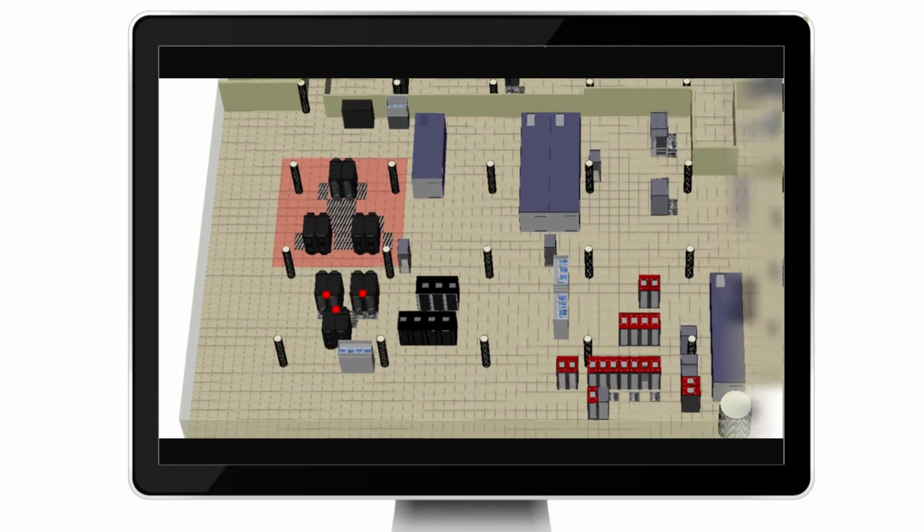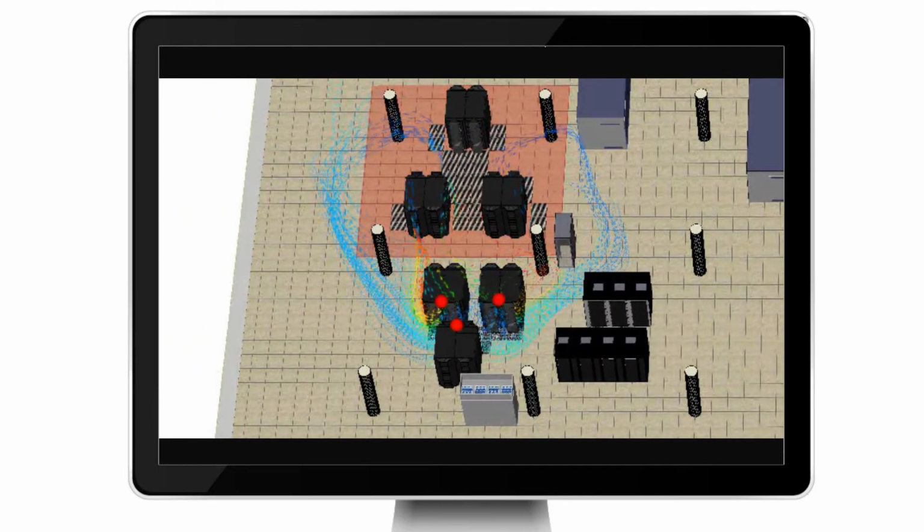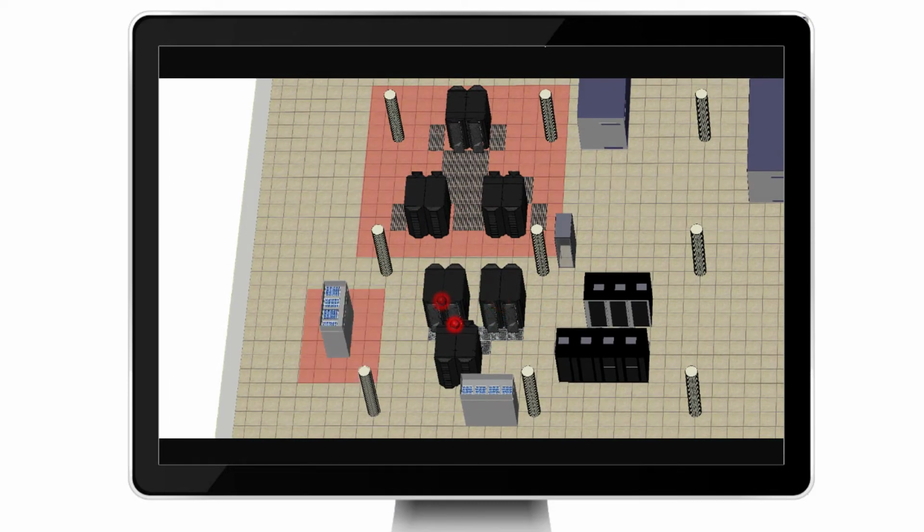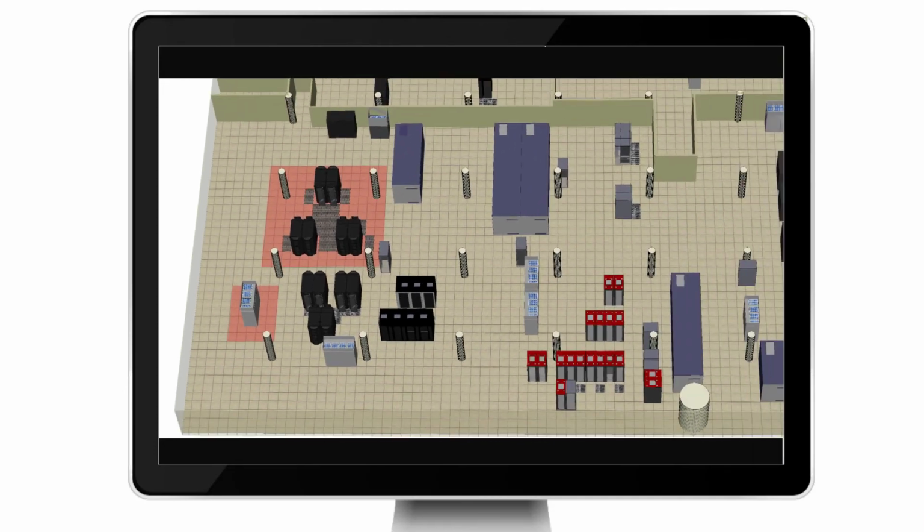After simulating, Digital Twin reveals something that we didn't know before. The likely configuration will fail temperature compliance by overheating IT racks in the adjacent aisle. Digital Twin's ability to mimic behavior helps us to avoid an IT service outage. It also reveals the cause of the problem and provides the foresight needed to design a solution. A new cooling unit will get rid of this violation, but at a cost that is much higher than planned after accounting for the new cooling unit.